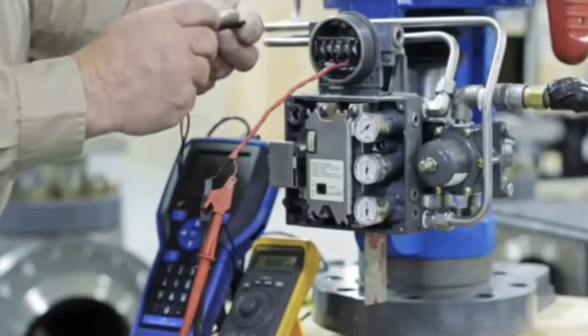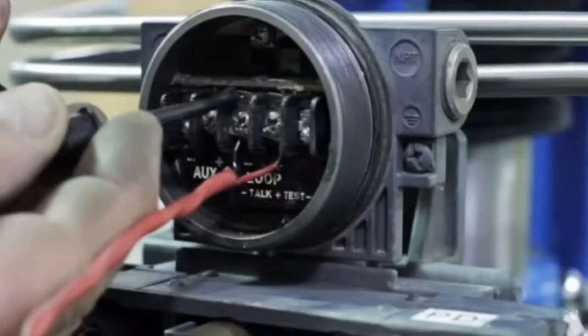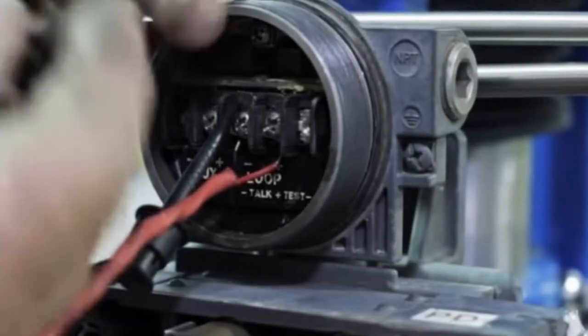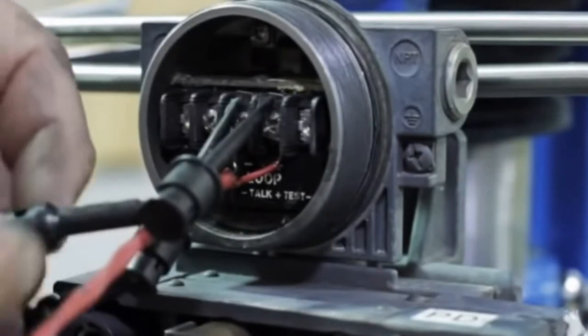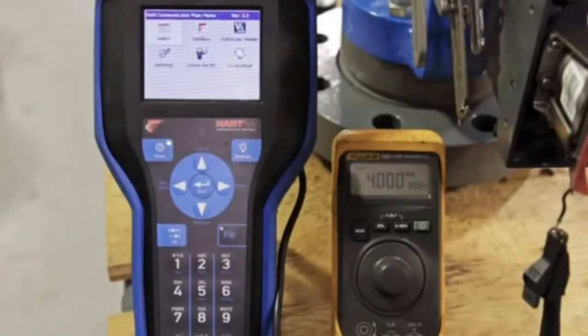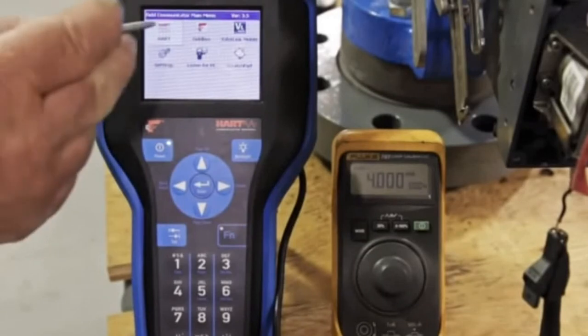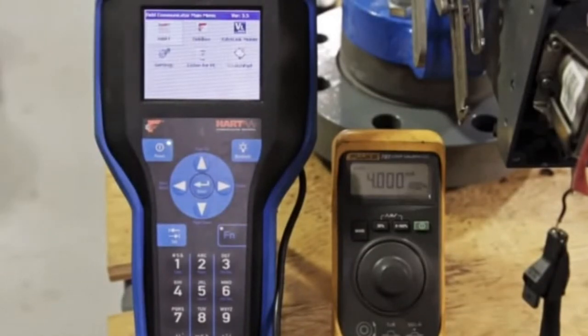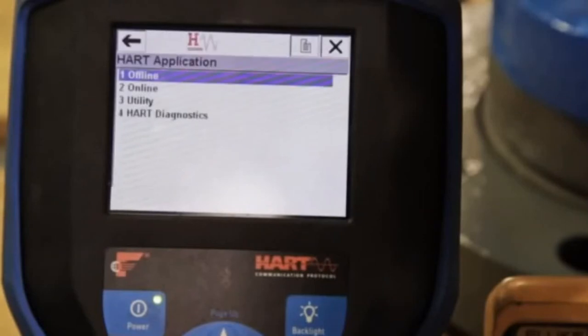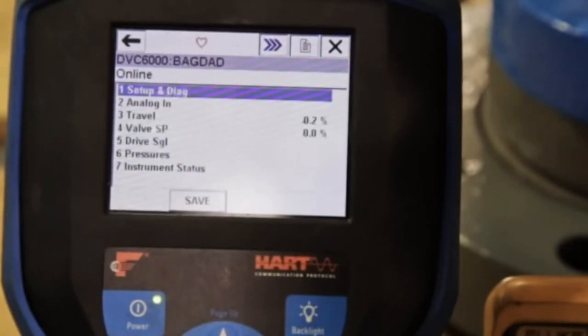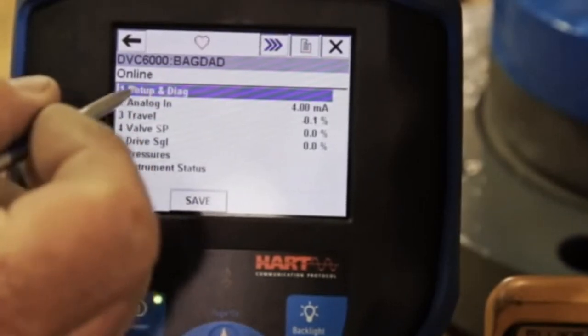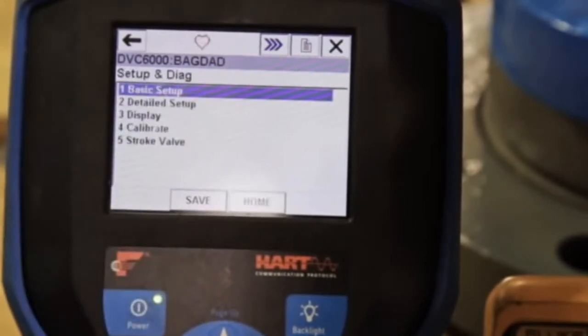Connect the 475 field communicator to the terminal box loop terminals as well. The beating heart graphic on the 475 handheld lets you know that communication has been established with the positioner. On the 475 startup screen, select HART. Select number 2 to get to the online menu using either the touch screen or the keypad. Select 1 for setup and diagnostics, and again for basic setup.